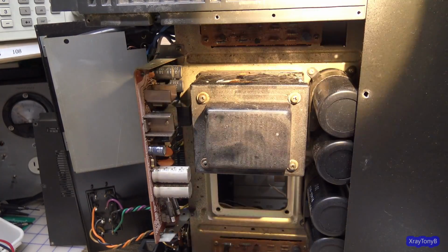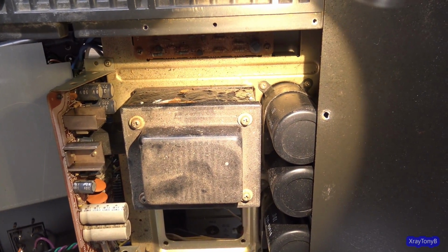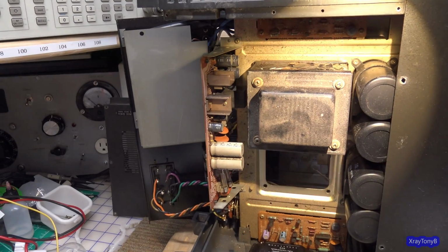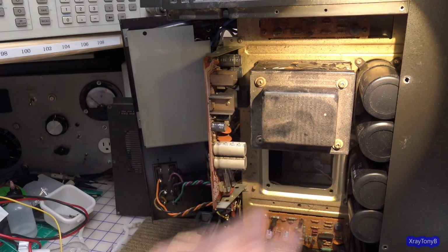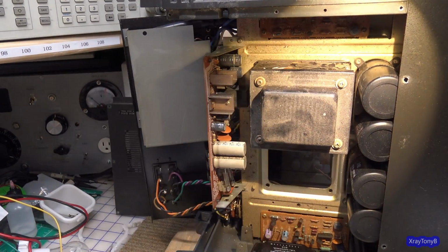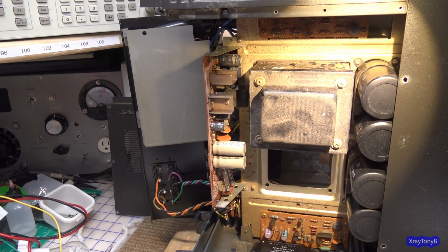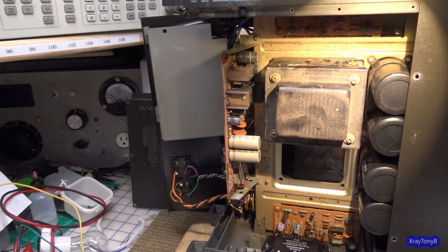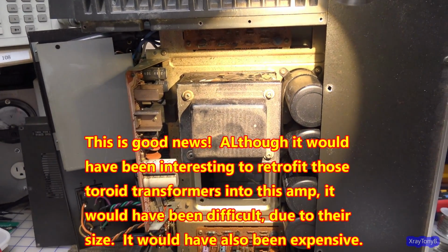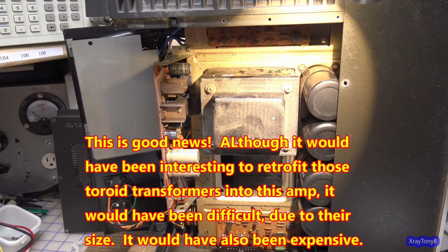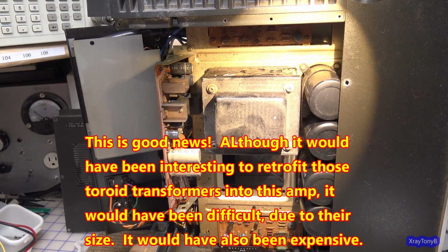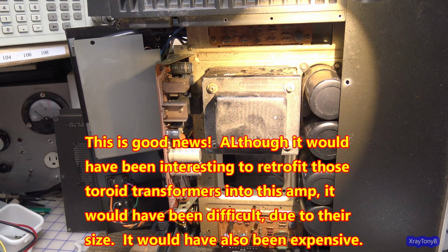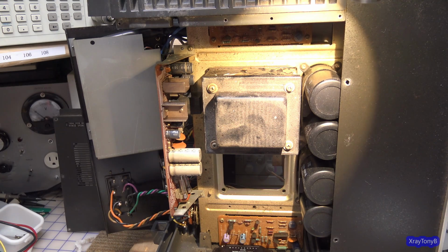I need to take that out and clean it - look how bad that paint is up there. So I'll probably pull this transformer, and since it works, I'll test it and everything, but since it works, I'll leave it together. I'll clean it and paint it the same way. While I have this out, that gives me a chance to clean the chassis. There's no rust, corrosion, or anything on the chassis that I can see. So other than a cleanup, which I think if I just do a little basic cleanup down here, I bet it'll come out really nice.